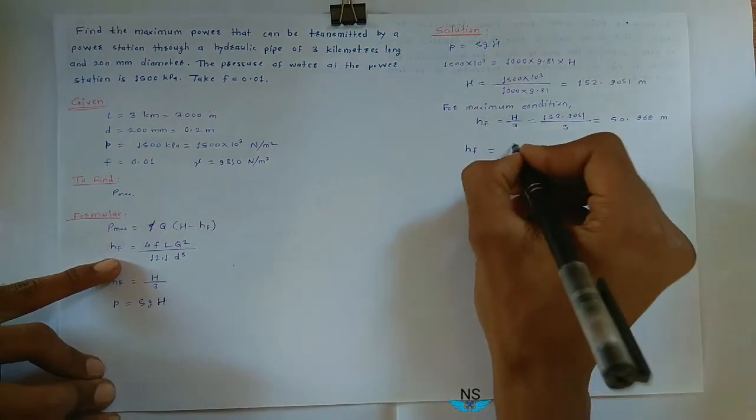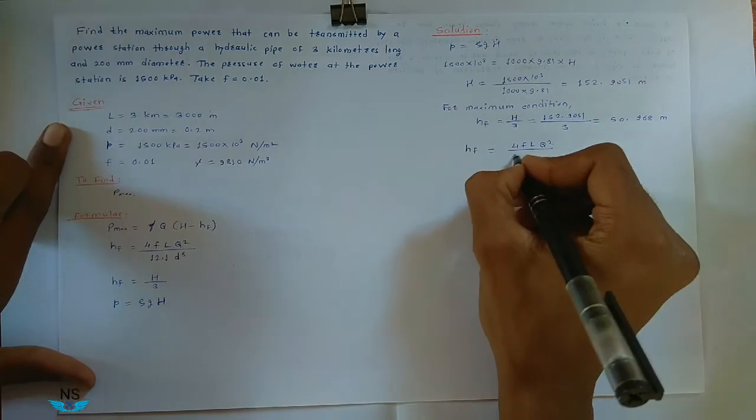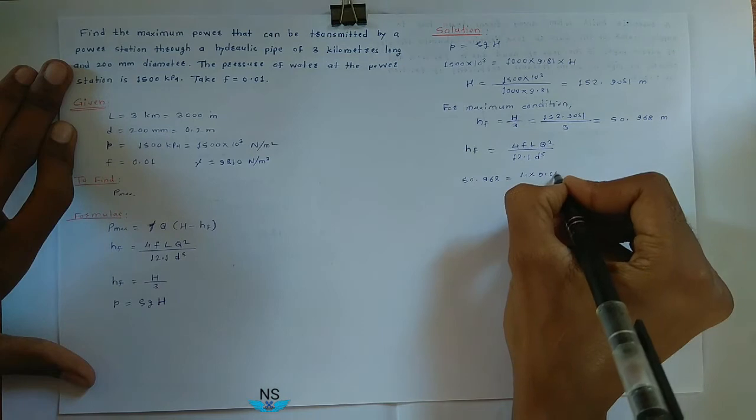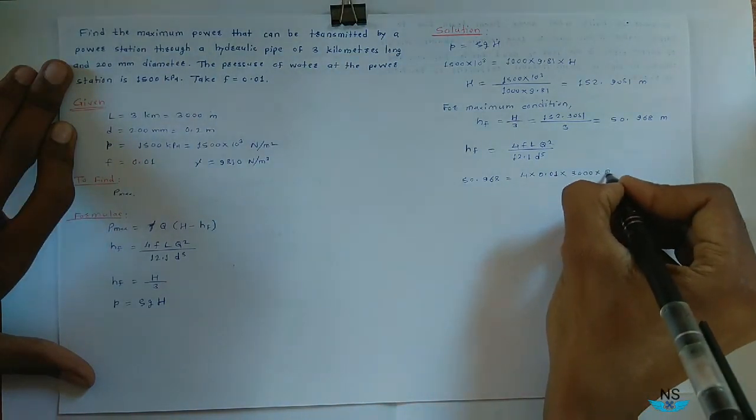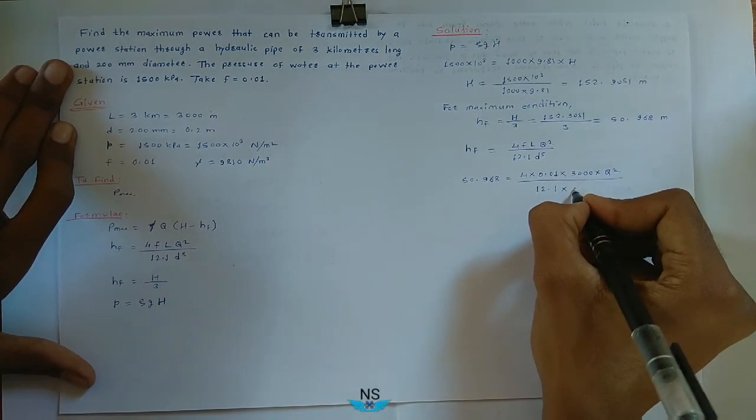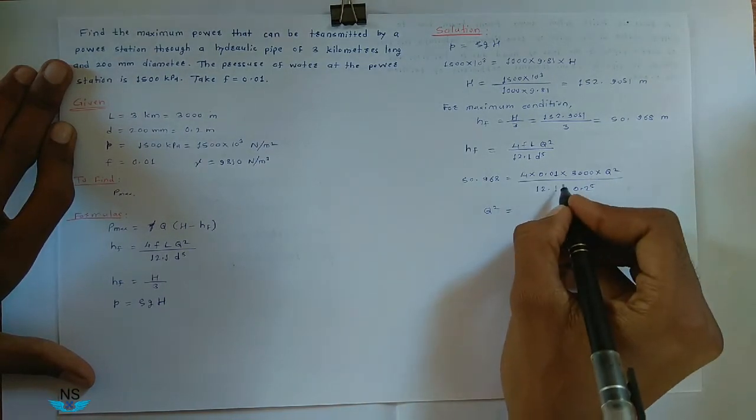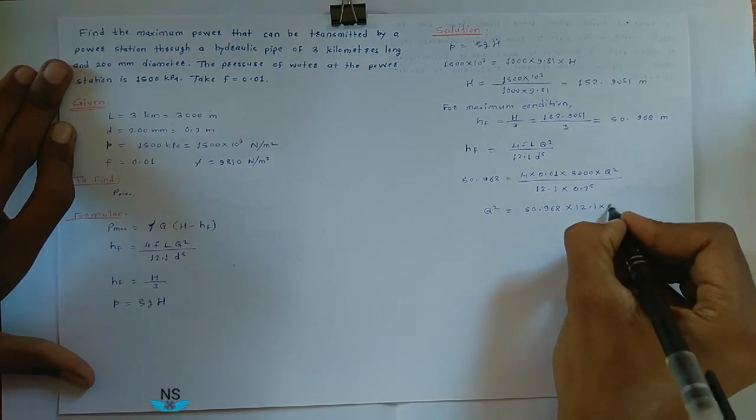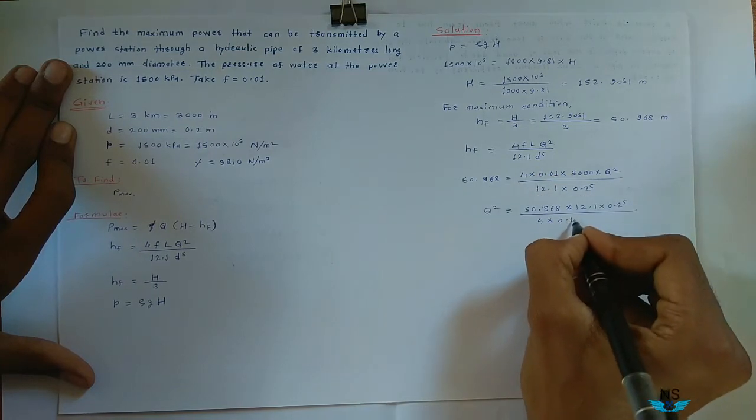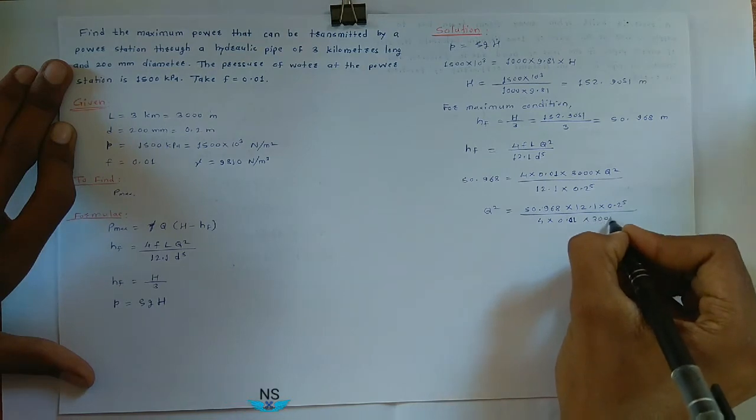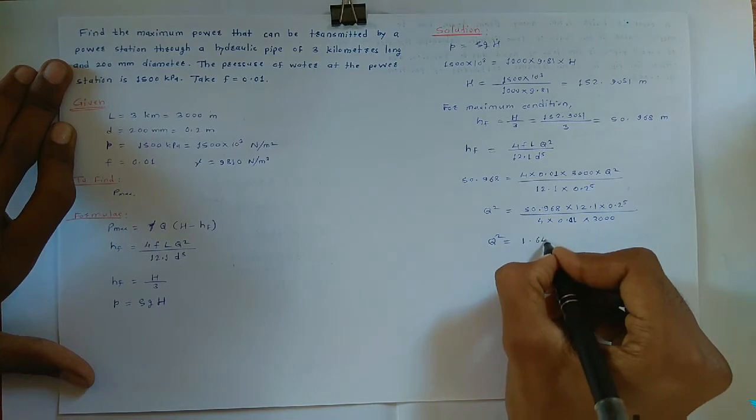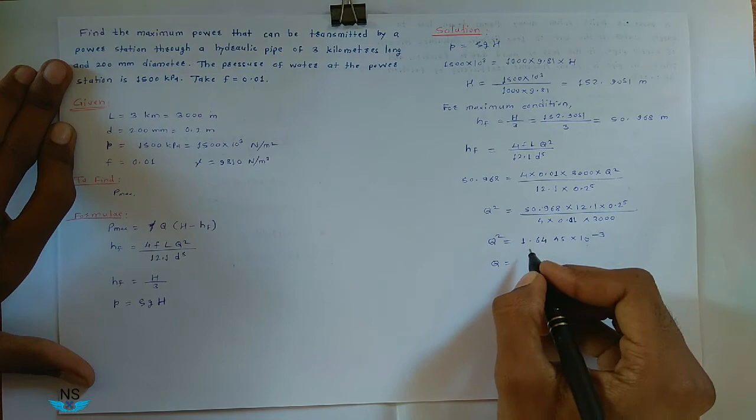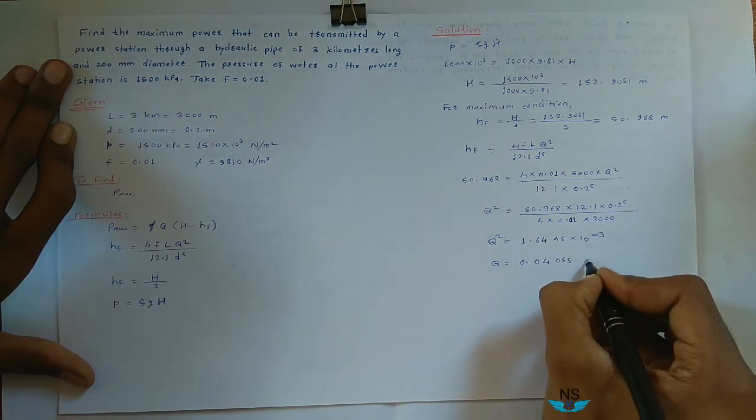After that, you have to find Q. So HF is equal to 4 F L Q square divided by 12.1 into D raised to 5. HF you know, 50.968, is equal to 4 into 0.01 into 3000 into Q square divided by 12.1 into 0.2 raised to 5. So Q square is equal to 50.968 multiplied by 12.1 into 0.2 raised to 5 divided by 4 into 0.01 into 3000. So Q square becomes 1.645 into 10 raised to minus 3. So Q becomes, take root of this answer, so Q becomes 0.04055 meter cube per second.